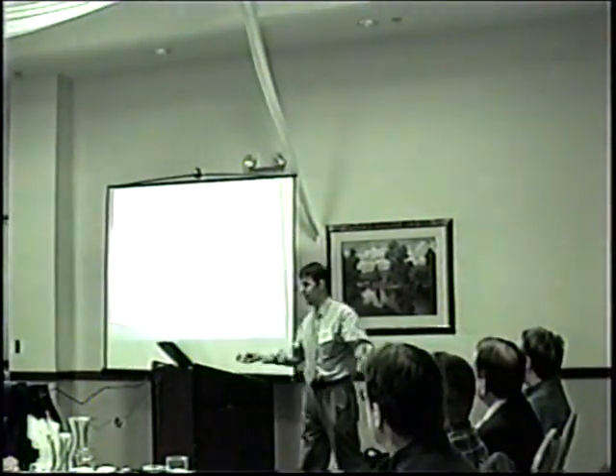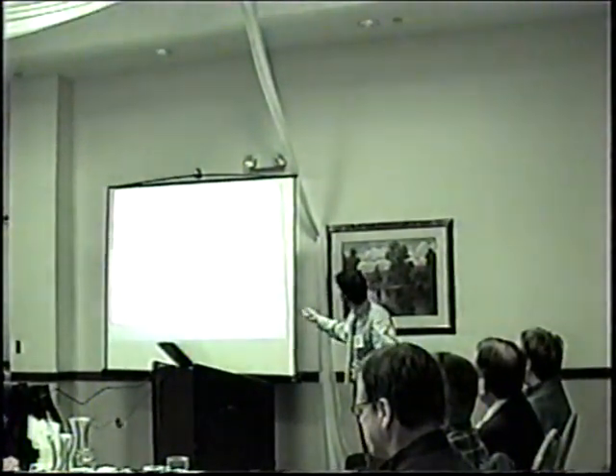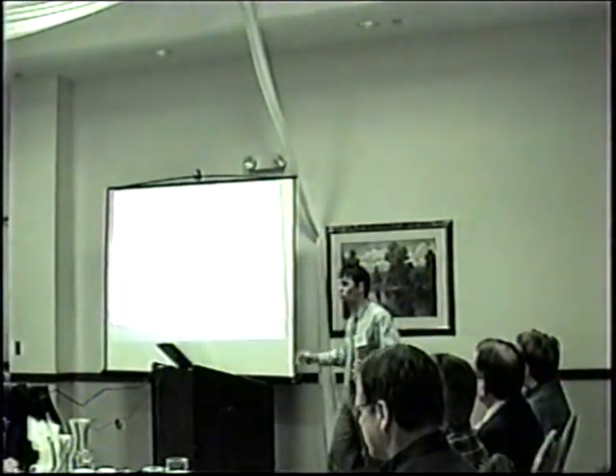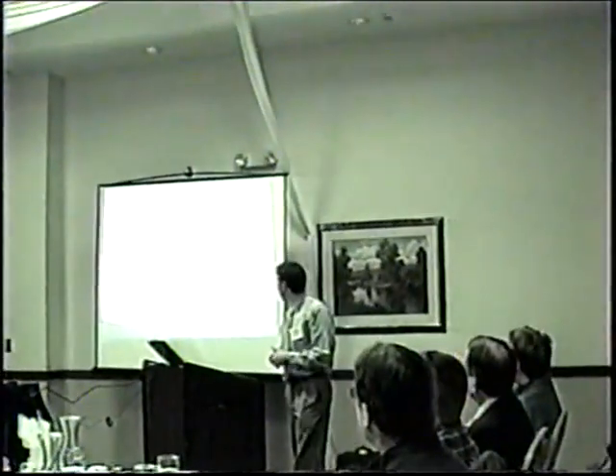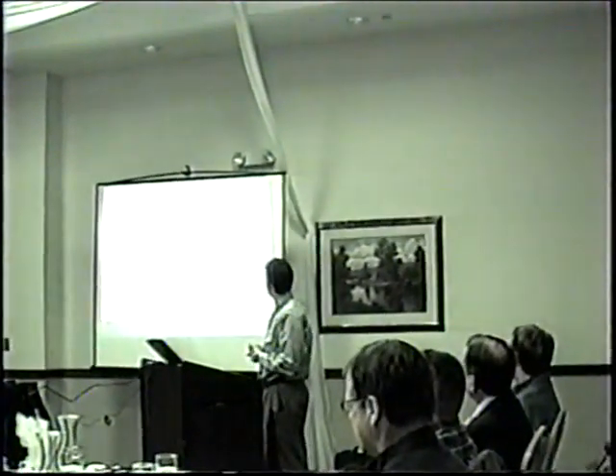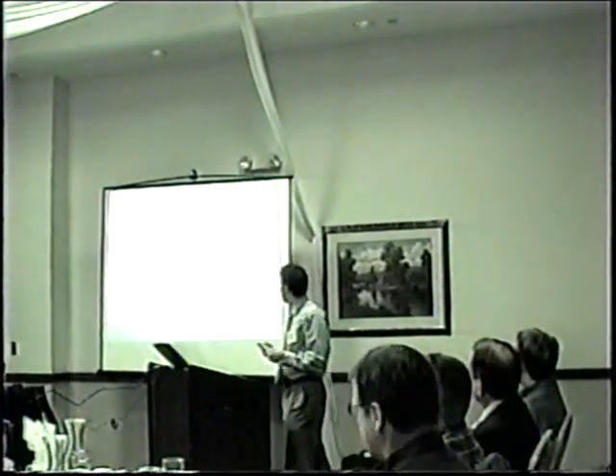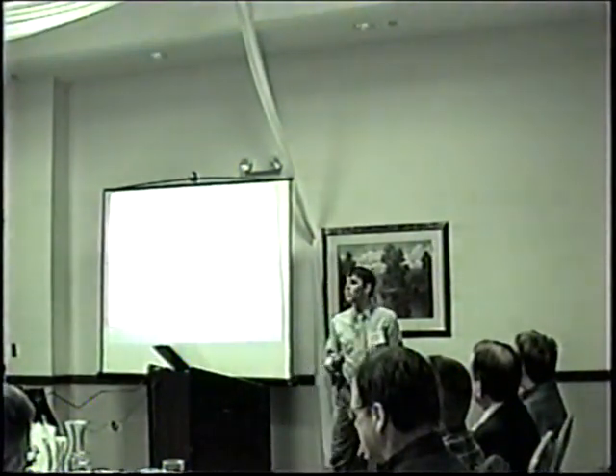So basically, they wanted kind of a 12-foot wide, 20... I'm not sure if that's interpreted to be on either side or not, but a 12 to 24-foot wide burned area, nothing more than that. Total water demand not to exceed 1,500 gallons a minute. Air temperatures at the ceiling greater than 1,000 degrees for no more than 5 minutes within any 400 square foot ceiling area, and the rack steel integrity must be maintained.